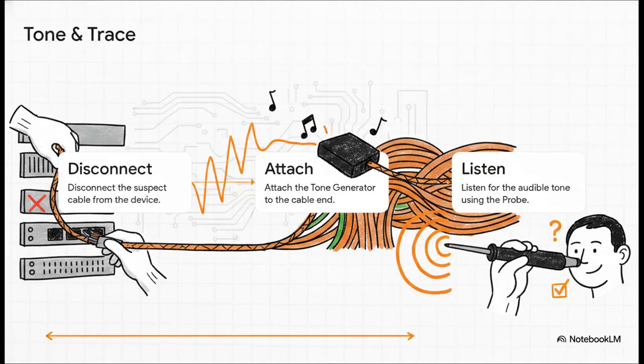Okay, let's walk through the actual sequence for tracing copper cables, the tone and trace procedure. Step 1 is to safely disconnect the suspect cable. Step 2, you attach the tone generator directly to that end of the cable.